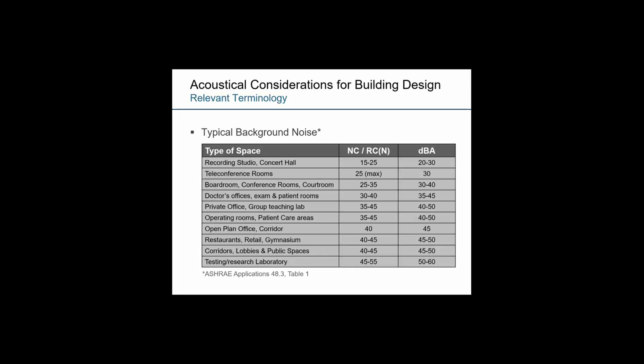Again, on some of the fundamental terminology, when we refer to noise and sound, we often use things like this table here, which is actually referenced out of the ASHRAE Applications Handbook. We speak of things like NC or RC or dBA, and these are single number references and easy ways to refer to the sound pressure within a space. Again, sound pressure is dependent on the environment.